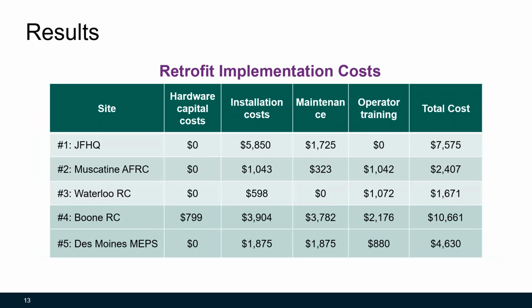The retrofit implementation costs include hardware capital costs, installation costs, maintenance costs, and operator training costs. For the hardware capital costs, only one site's failed VFD needed to be repaired, which cost about $799. And the installation cost is basically the program customization cost. And the maintenance cost is troubleshooting and repairing some of the VAV box problems. We also provided operator training to the facility managers because they are not familiar with the static pressure reset strategy. And the total retrofit implementation cost is between $1,600 and $10,000.